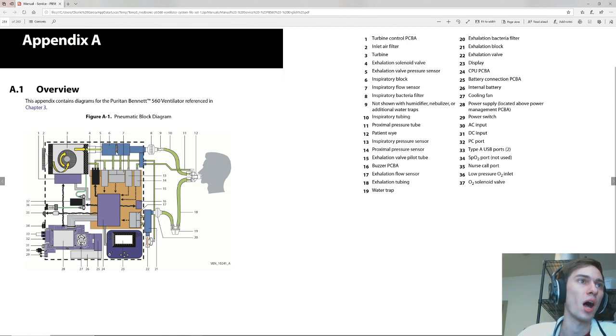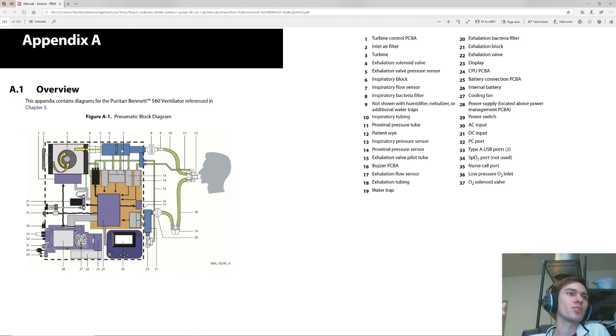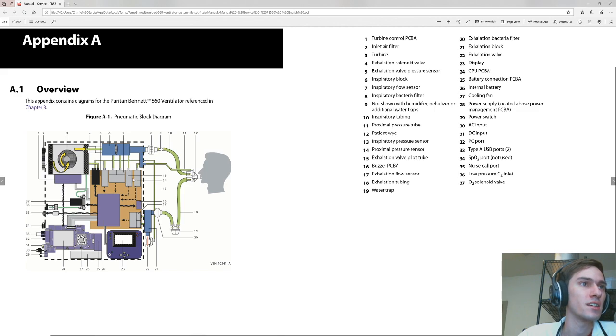So there's probably some known pressure drop over this grating. And then by knowing the pressure upstream and downstream, they can get the volumetric flow rate. Okay, that makes sense. So just some ideal gas law type stuff. This block right here is 13, which is the inspiratory pressure sensor. So I bet this is how they're triggering a breath, when the pressure on this falls, they are delivering a breath. 14. So 14 connects here. No, so 13 is not connected to the patient. 13 is upstream of the patient's breath. So sensor 13 is just measuring the pressure in this and probably regulating that. So sensor 14 is connected to the mask on the patient's side downstream of the check valve.